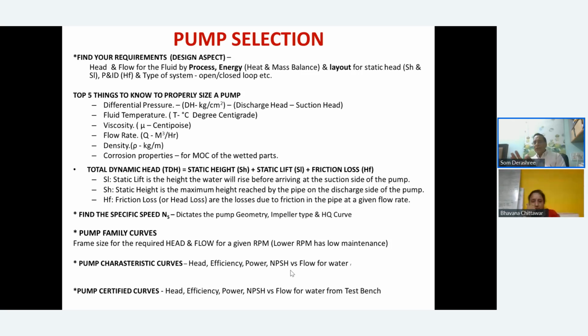So it's always preferred to have a lower RPM because it leads to lower wear and tear and lower maintenance. So the lower the RPM, the better. But if you have a very low RPM, you will not be able to develop a proper head through a centrifugal pump, so there is a trade-off to find the actual RPM required.